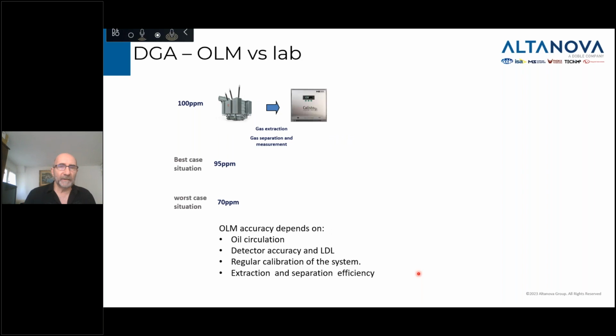The next one, developed over the last 25 years, is online monitors. Online monitors fix a lot of the handling. You have mostly no handling system, because those online monitors circulate the oil directly themselves. So when the oil comes from the transformer directly to the online monitor, there's no chance of losing gases. Depending on the system accuracy of your online monitor, in the best case scenario, if you start with 100, you should end up with results of around 95, 94, 93, with a system accuracy of around 5 to 6%.